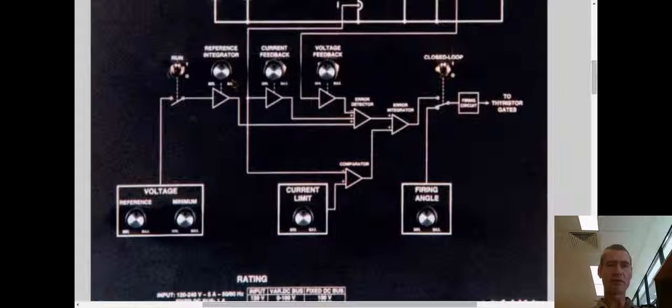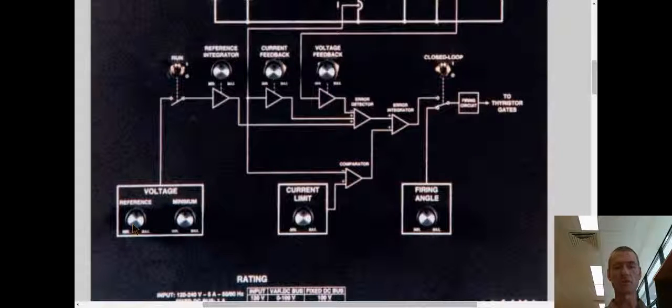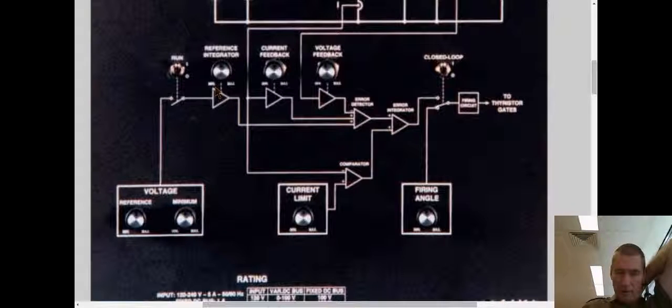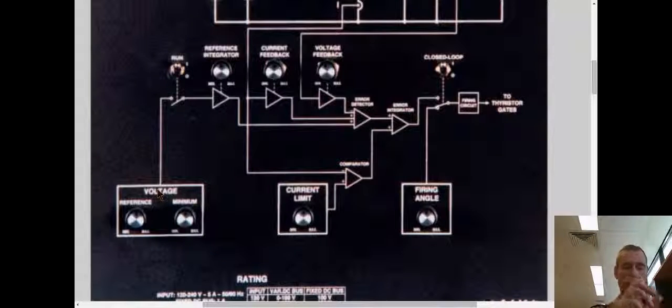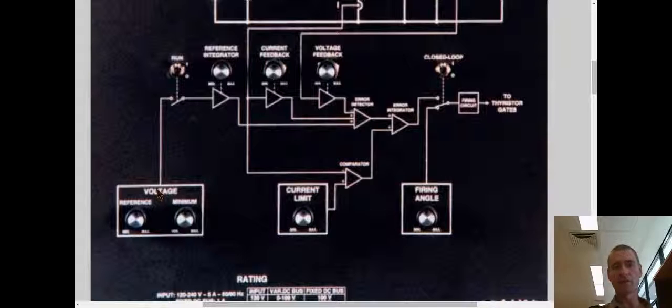The reference integrator determines how quickly the control system responds to changes in the voltage reference. So if the reference integrator is on minimum, that means there's a minimum amount of integration on that input signal. So if you do a sudden change, then a sudden change gets transmitted straight through into the control circuit. And that could lead to the circuit breaker tripping.